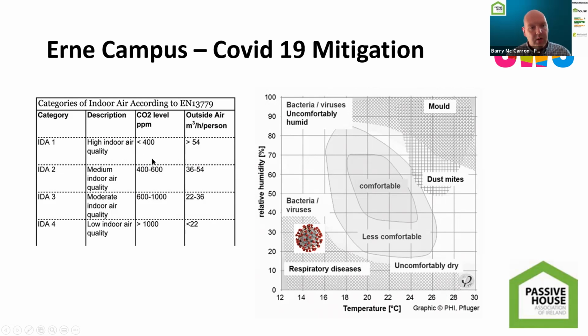Just a note on the other indoor air qualities specified here: 400 to 600 means you need to supply air at about 36 to 54 cubes per person per hour. That's not really sustainable because the air is forced at that point, making the building too dry. And on category 2, a note on climate change and CO2 levels - the outdoor air of the world, quite soberingly, doesn't even meet the first category anymore, because globally we're about 415 CO2 parts per million, so we don't even have that outside now.